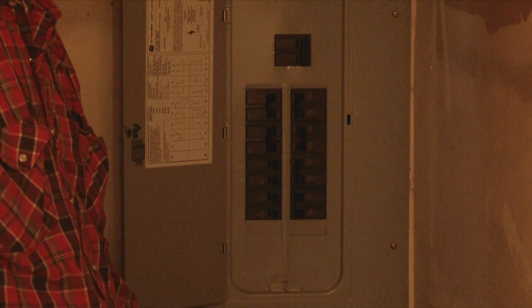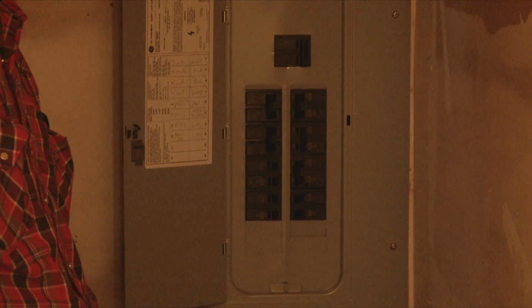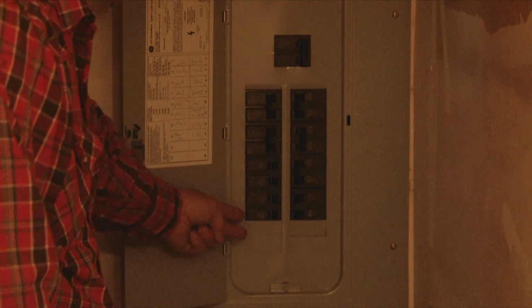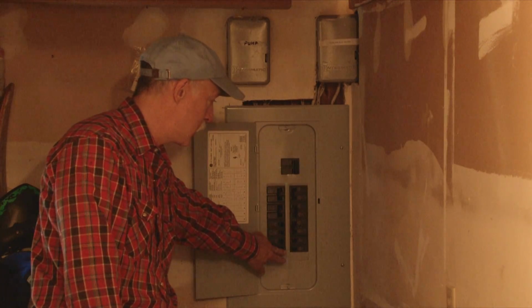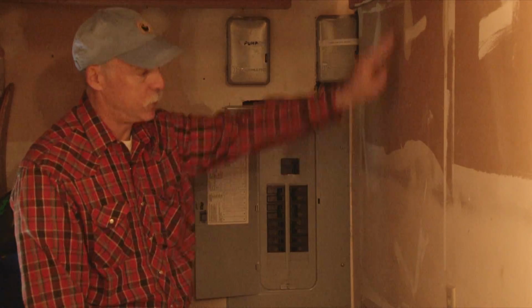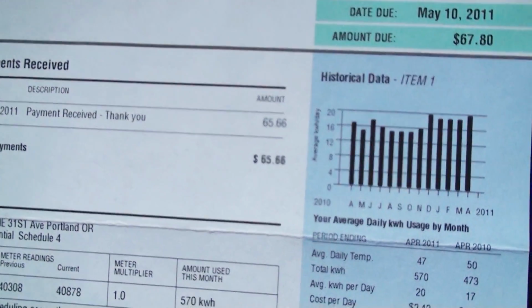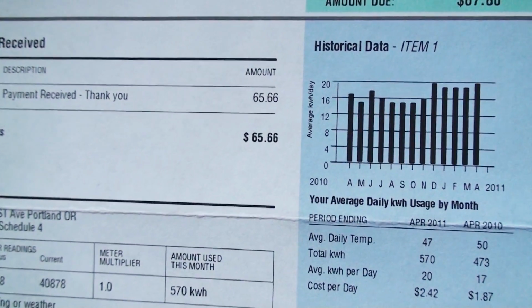They'll identify the make of the electrical panel, whether it's been installed to today's code, and if there is room on the panel for new electrical breakers. They also need to identify wall space to locate the inverter, the disconnect, and the new production meter. Lastly, the technician will ask the homeowner for a copy of a utility bill in order to gauge the homeowner's usage and estimate the potential offset of the new system.